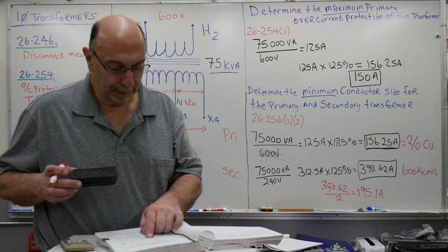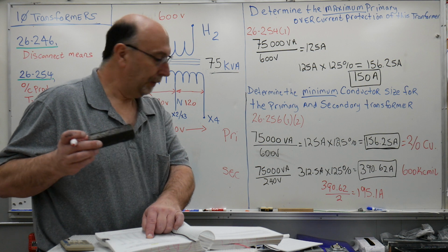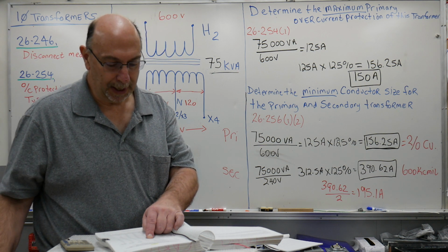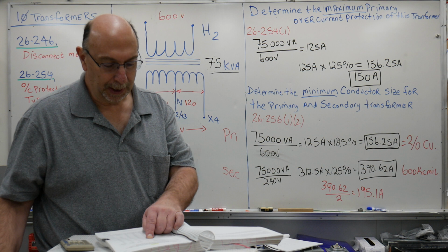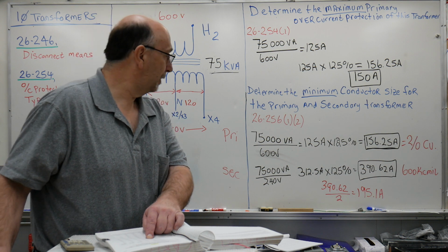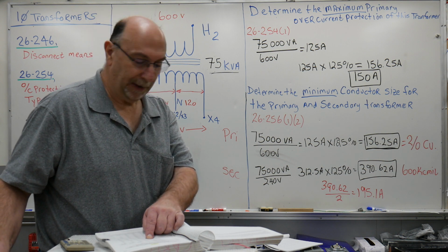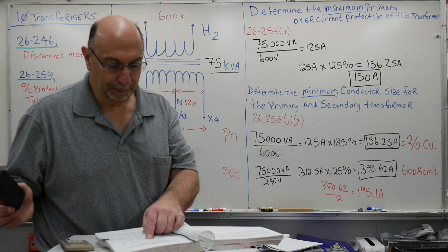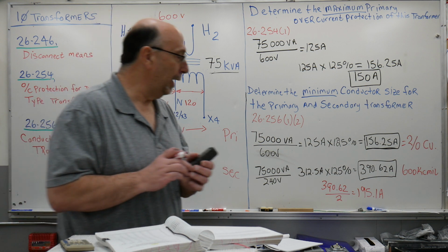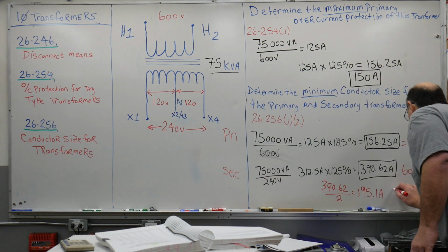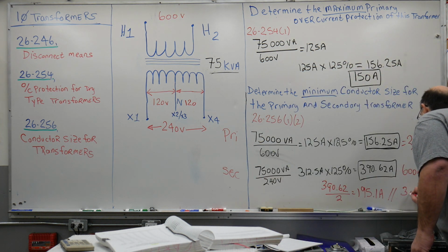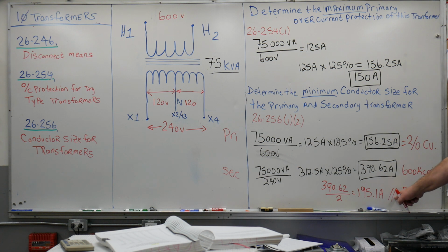And take a look at 3/0. 3/0 is good for 200 amps, which is obviously more than the 195.1. So wouldn't it be easier to run parallel runs of 3/0? So the 2 little lines there means 2 runs of 3/0. Anyway, so that concludes this 75 kVA transformer.